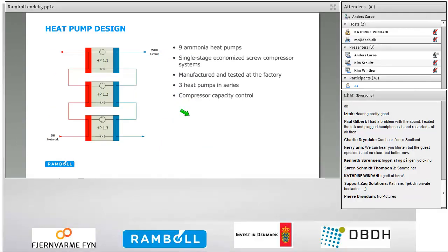Now, moving more into the technical side of the heat pump units, as Kim said earlier, there's 3 ammonia heat pumps per group with a total of 9 heat pump units. Ammonia was chosen as the refrigerant due to its superior energy performance and also due to Danish restrictions on synthetic refrigerants. All the units are single-stage screw compressor systems with economizers, and in this instance, screw compressors were the most feasible solution due to the size of the plant and the expected operating pattern. The screw compressors are almost the same, which then reduces the amount of spare parts required for the plant.